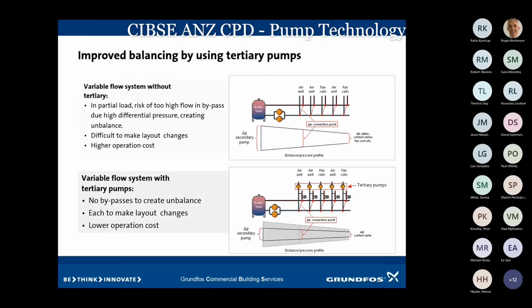Here we have a couple of circuits, and the top one here is a variable flow system, primary only. So the primary pump requires a certain pressure drop, as you can see below the buffer tank here, to get the water through the whole system. It's got to feed the water through the tank out into the pipe work to each unit, get it through there and then back in again. So that pump has to produce a reasonably high pressure to get it through to that system. And then the valves will be modulating at each unit and on the coils.